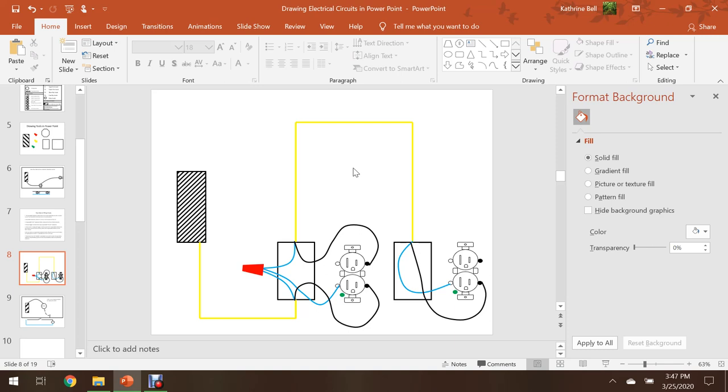As long as it's not a multi-wire branch circuit, which is beyond the scope of this tutorial, that would affect our neutral conductors. The last thing we need to do is we need to ground everything. In wiring that we teach in agricultural education, typically we're talking about surface-mounted metal boxes. The National Electrical Code refers to these as normally non-current carrying enclosures. So any box that is metal that contains electrical conductors or devices would be a normally non-current carrying enclosure. As such, the code requires that we connect these boxes and devices to our service entrance panel grounding bus.